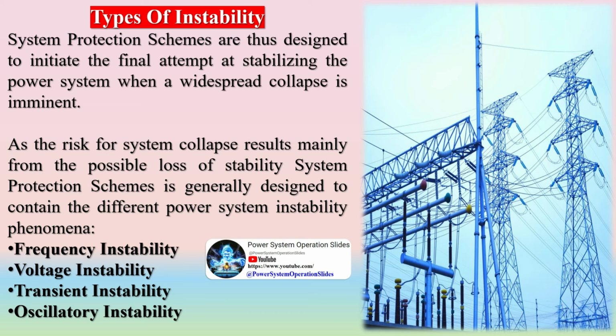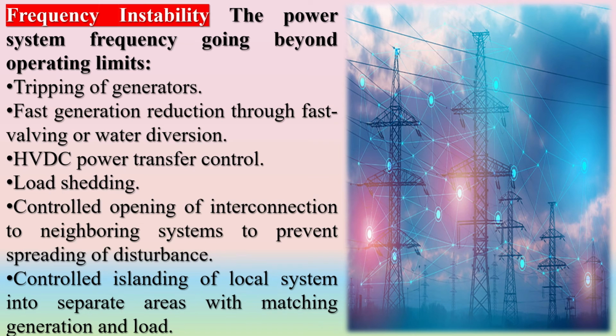SPS design criteria. The four main design criteria which should be used for SPS according to CIGRE are: dependability, the certainty that the SPS operates when required, that is, in all cases where emergency controls are required to avoid a collapse. Security, the certainty that the SPS will not operate when not required, does not apply emergency controls unless they are necessary to avoid a collapse. Selectivity, the ability to select the correct and minimum amount of action to perform the intended function, that is, to avoid using disruptive controls such as load shedding if they are not necessary to avoid a collapse. Robustness, the ability of the SPS to provide dependability, security, and selectivity over the full range of dynamic and steady-state operating conditions that it will encounter. Another very important design criterion that should be considered is reliability of SPS.